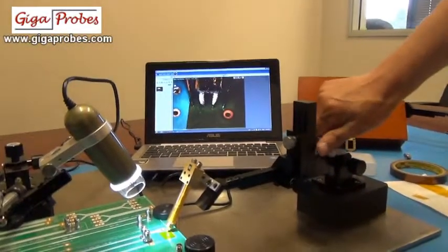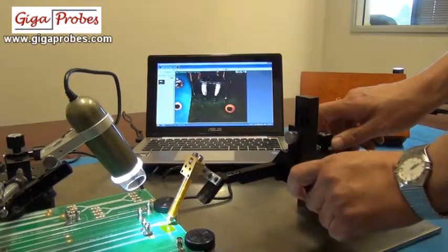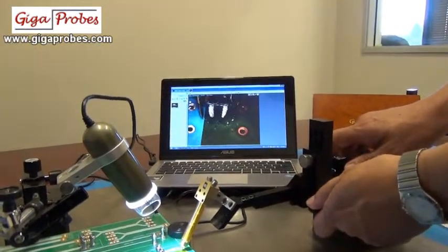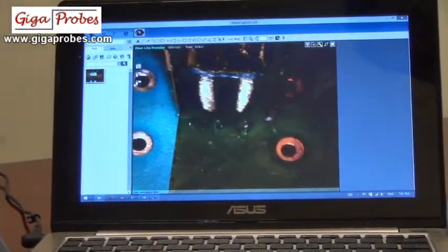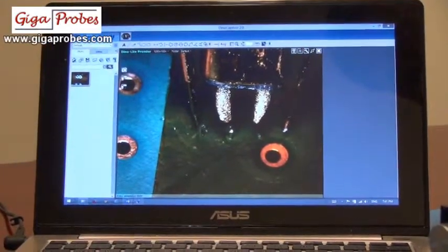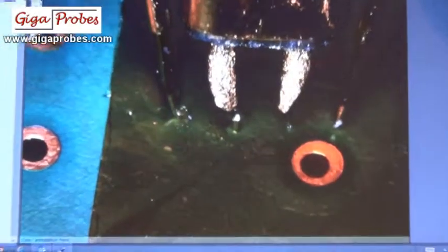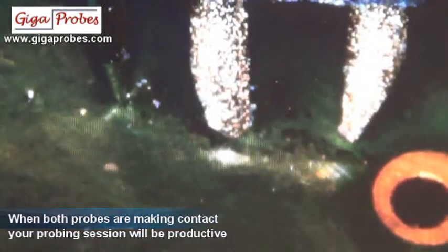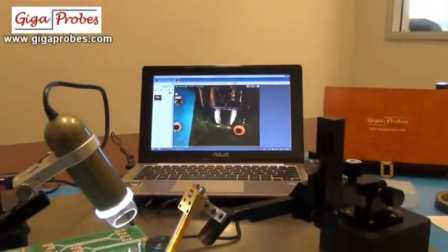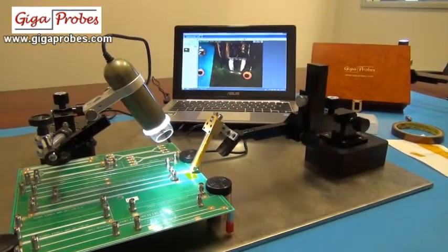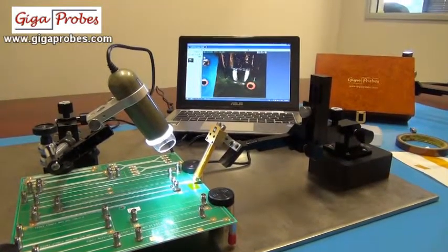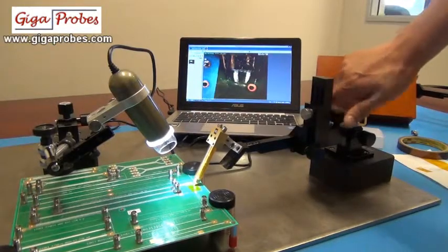So now what we'll do is we're going to back off the probe using the z-axis of the TP600 Easy Positioner, and we're going to adjust the theta control, as you can see, in order to bring the left probe down. So hopefully both probes will make contact with the Mylar, and you'll get some feedback by looking at a ballooning effect when the probes make contact. So see, now both probes have a kind of like a white light or a ballooning effect, so knowing that both probes are now making contact at the same time. So when we bring the probes over the pads that we need to make measurements on, we have a high confidence that when the probes hit the differential pads and grounds that we're going to get a measurement.